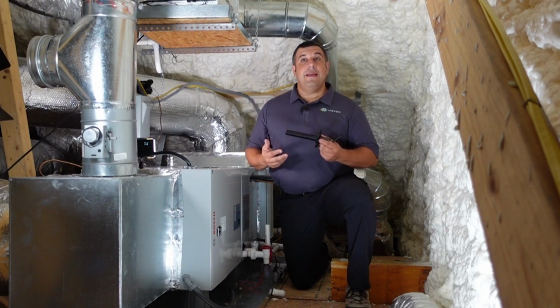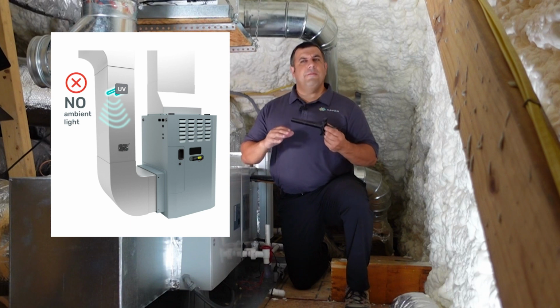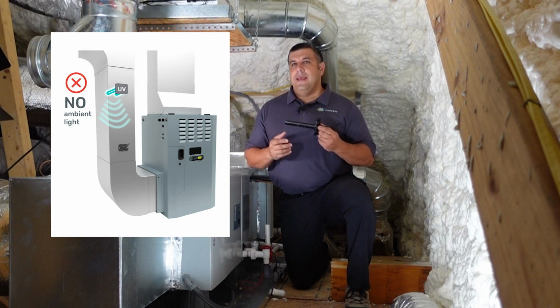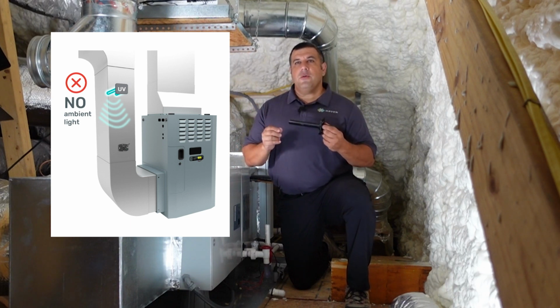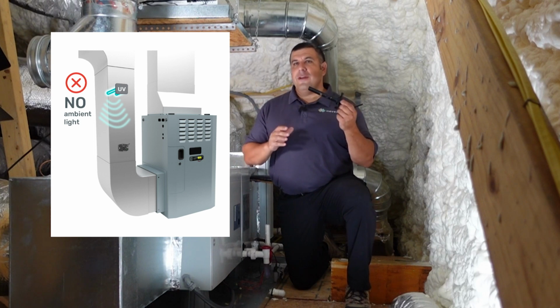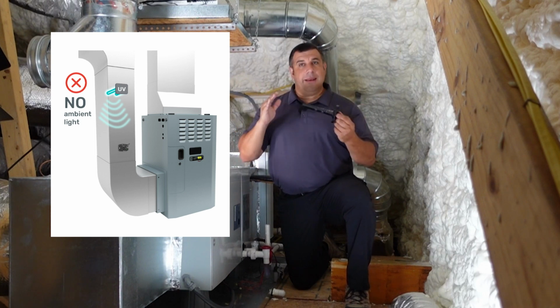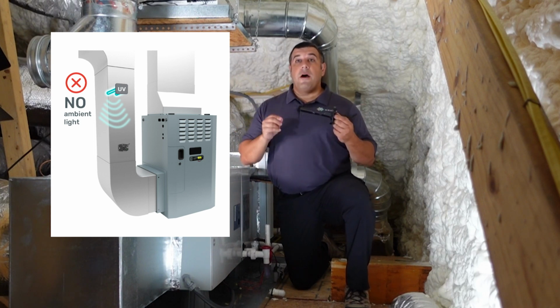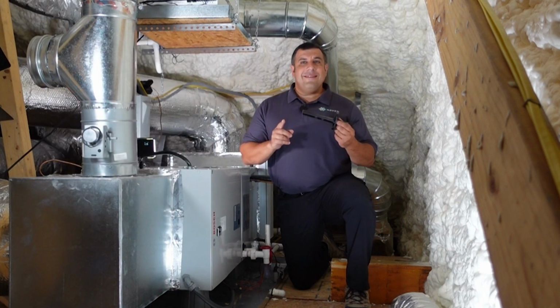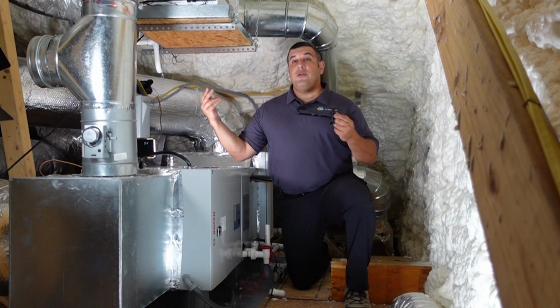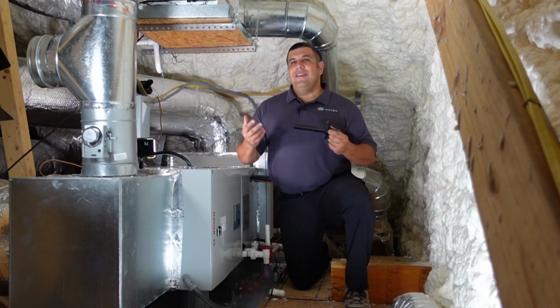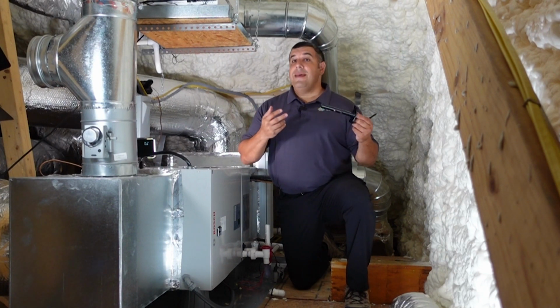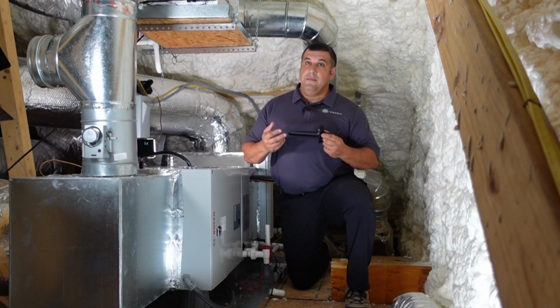As for ambient light, the monitor sensors require complete darkness to function properly. Ambient light in the return duct will cause the laser particulate sensor to flatline or act sporadically. It can also throw off other sensors' readings. This means that the monitor cannot be installed next to a UV light, but most UVC systems manufacturers recommend installing in the supply duct anyway.